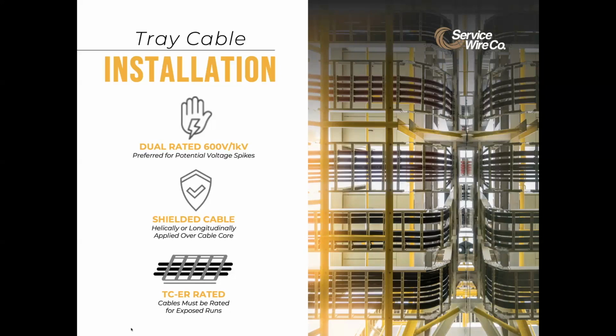Service Wire's tray cable is also TC-ER rated per the National Electrical Code. It is permitted to transition up to 6 feet without continuous support and exposed into free air. This allows the cable to transition from the cable tray to a motor, avoiding the use of flex conduit.